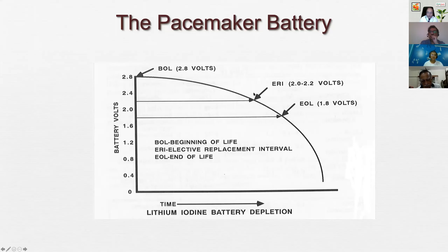Usually there are 2 points in that journey. One is called ERI, which is the elective replacement indicator, and that is the time when we want to replace the pacemaker. The second point is EOL, that is end of life, when the pacemaker will stop functioning. We don't want the pacemaker to go to EOL, and that's why it's very important to have a regular follow-up of the pacemaker battery. Whenever the pacemaker reaches ERI, we must change it. Usually there is a gap of 3 to 6 months between the two, so there is enough time for the pacemaker to be detected at ERI, and then we can change the battery.